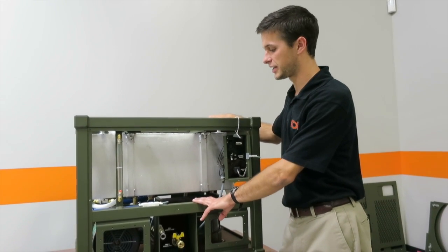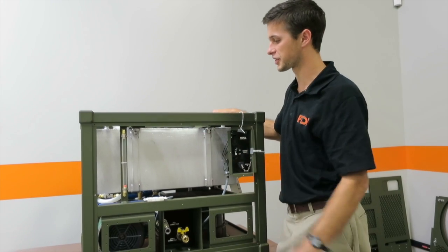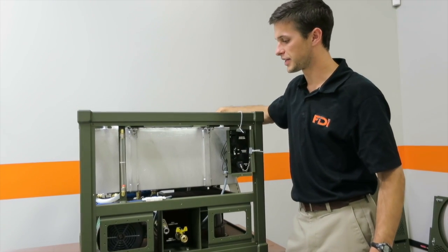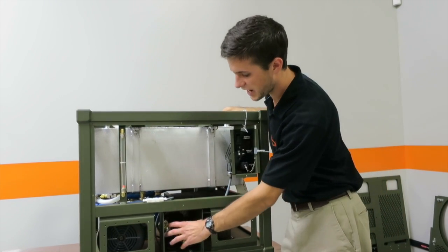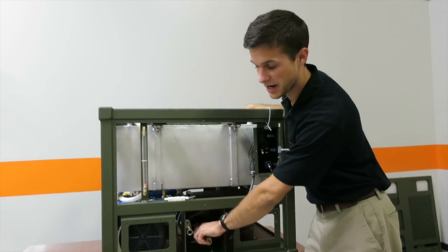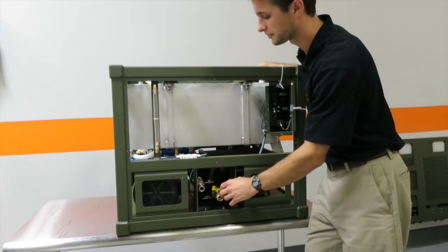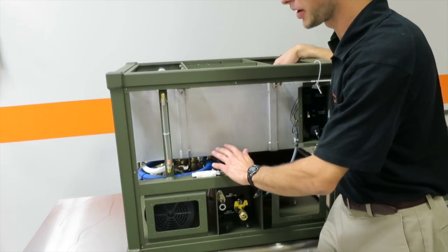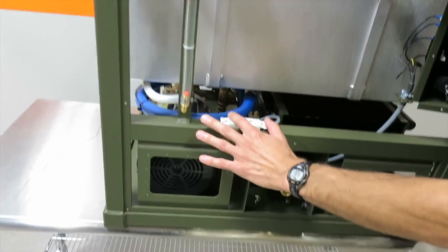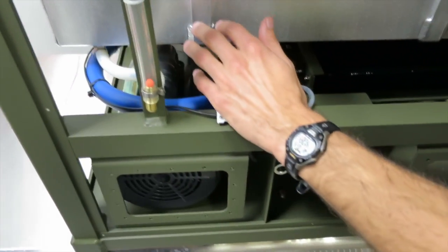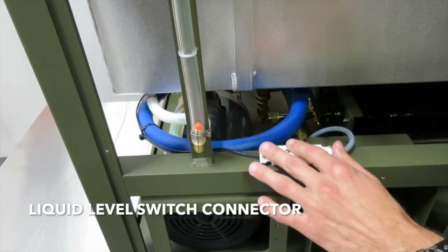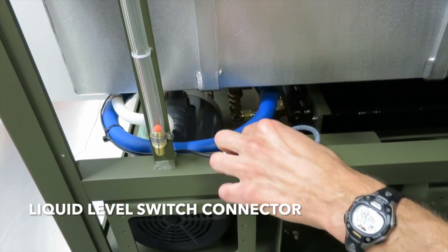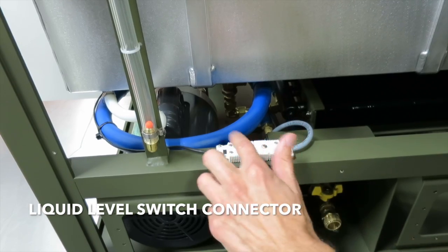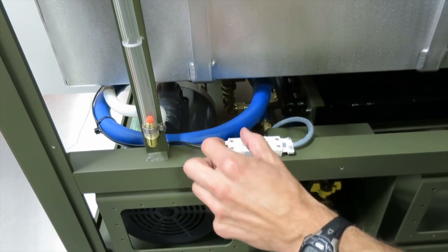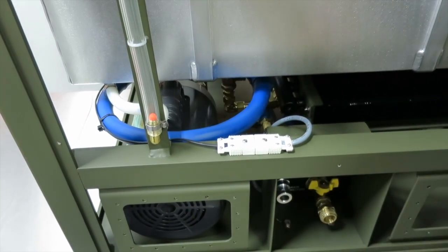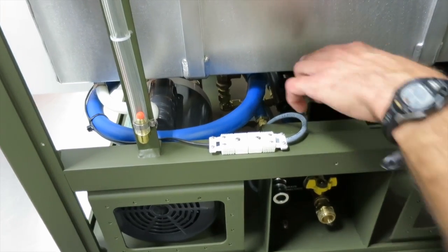Alright, we're talking about the internal components now on the water recovery system. On the side with the hose hookups down here, the drain connection box down here, we're just going to talk about two components. Right here we have the switch connector for the liquid level switch. Whenever you need to switch that out, just pull those two screws up and you'll be able to replace everything from this side of the connector over on down to the liquid level switch.